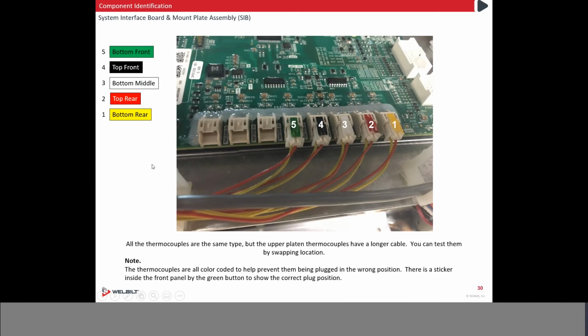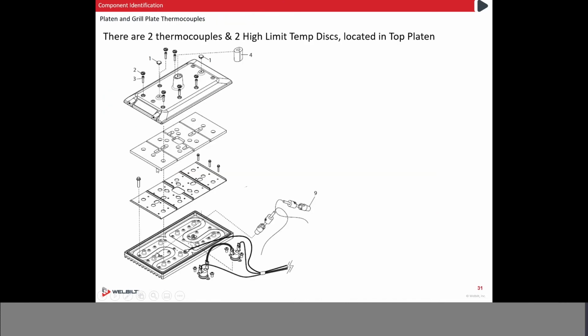Thermocouples, again, don't forget, we can swap thermocouples if there's a temperature-related problem. We can swap the SIB board to confirm if there's a temperature-related problem. What's different? Here's something that's different. In your Platen area, the thermocouples go into the Platen, just like the other grill, and we have two safety thermostat discs.